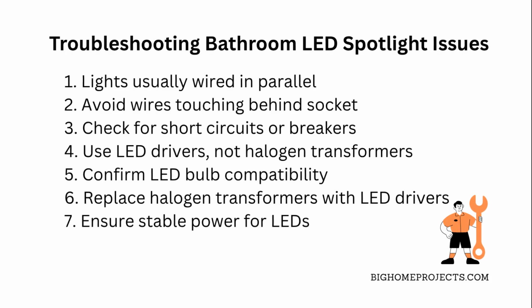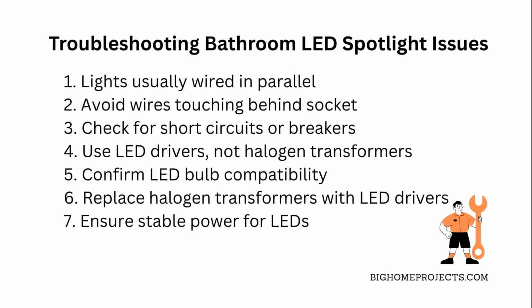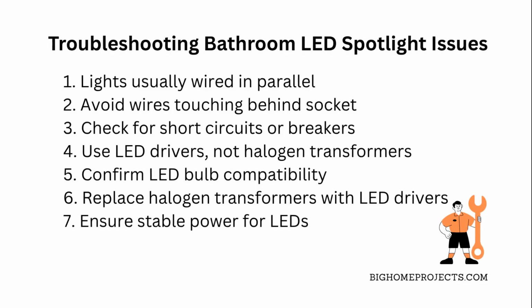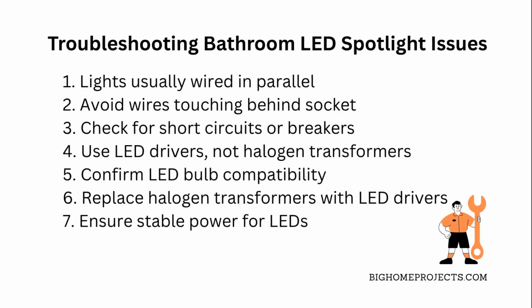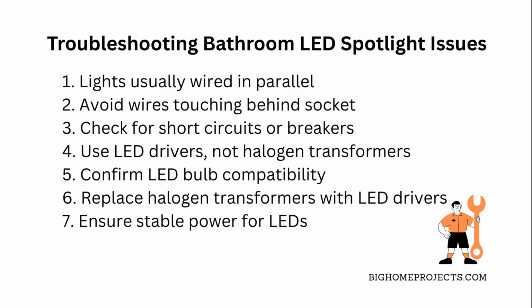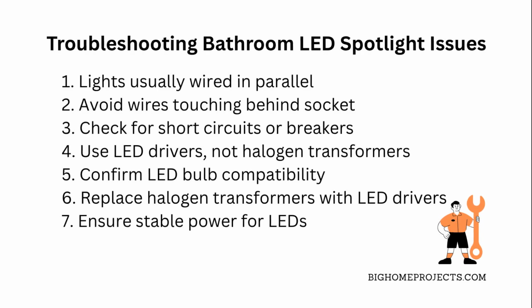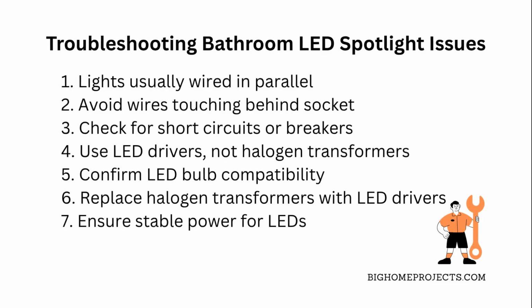Usually, spotlights on the same switch are wired in parallel, so each gets full voltage individually. But those wires behind the socket touching? That's a red flag right there. When wires touch, especially live ones, it can cause short circuits or trip breakers, which might explain why both lights are off. Plus, you mentioned you've got 230V mains feeding into a halogen transformer stepping down to 12V for your bulbs.